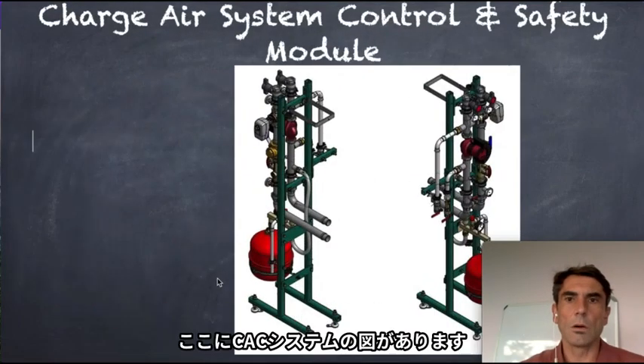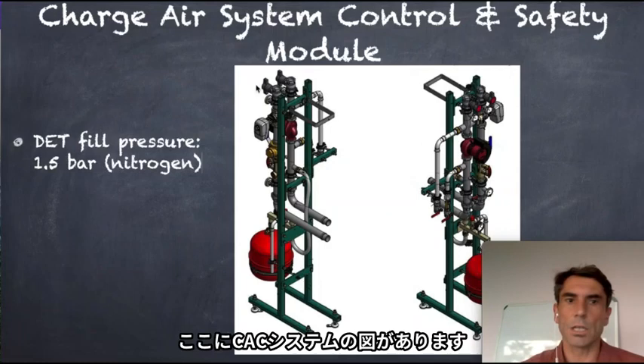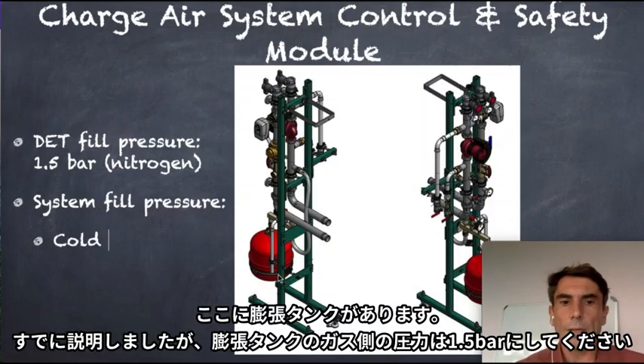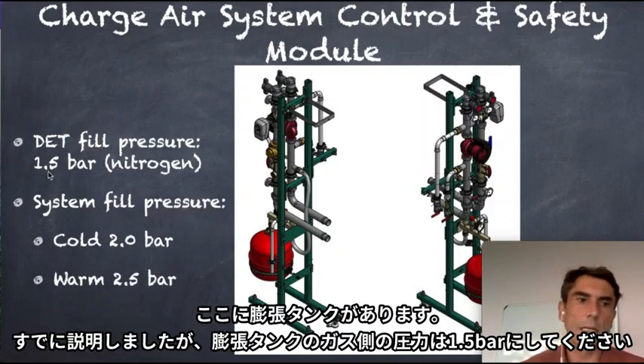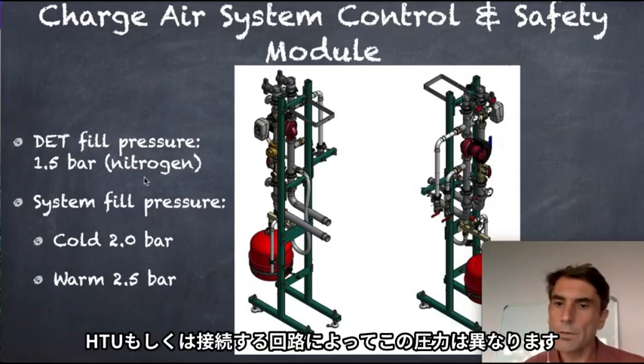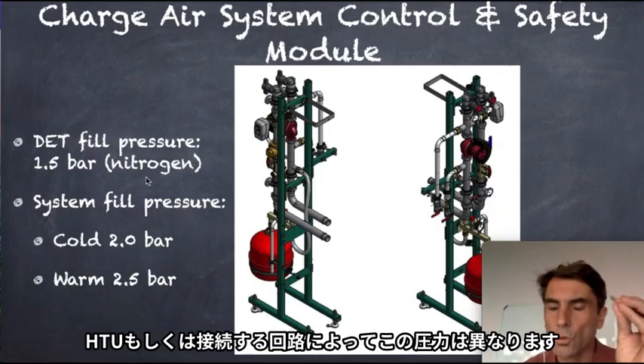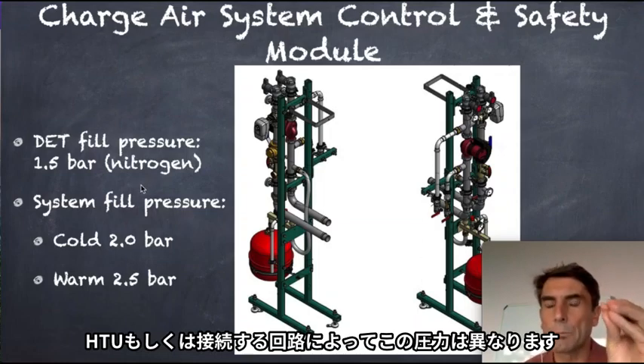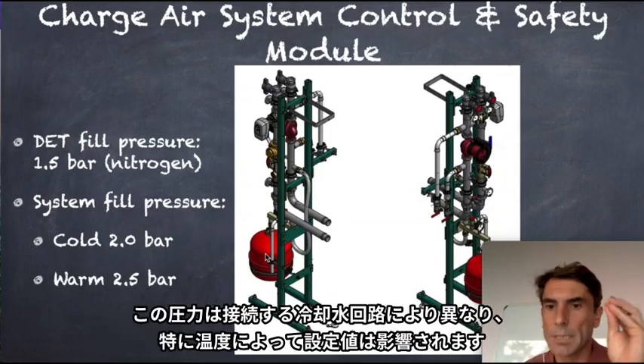Okay, so we have here the charger safety module. We have here the expansion tank underneath. The expansion tank needs on the gas side a pressure of 1.5 bar. It's different to the HTU. So different cycles will have different pre-pressure on the gas side of the expansion tank. Please keep that in mind.